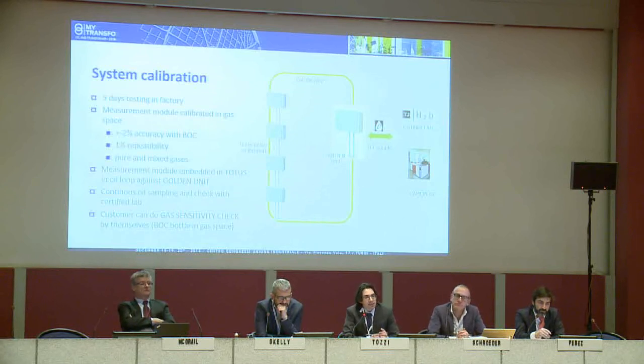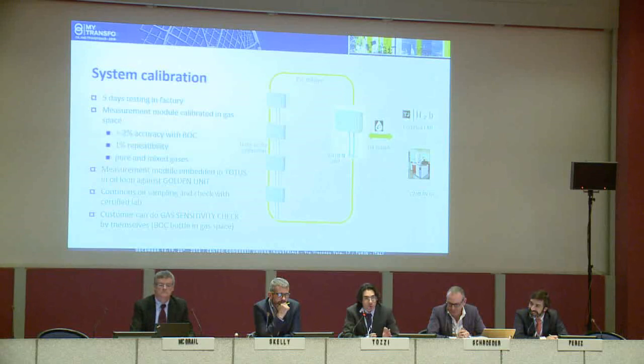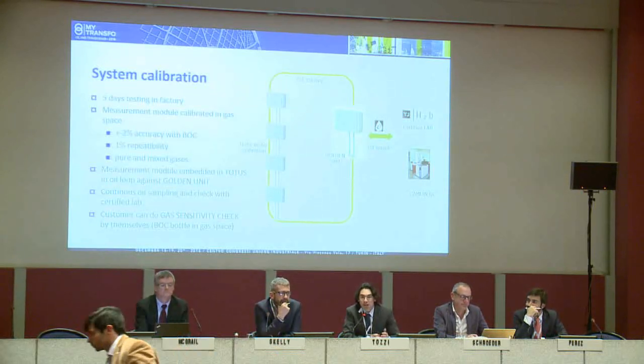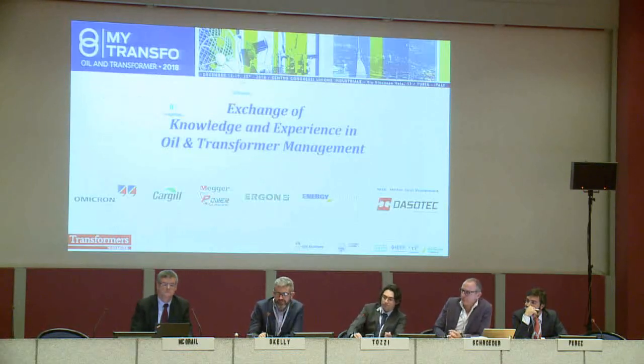Say that in some countries, we have to do a similar process, but using other laboratories, because, for example, in the Far East or Latin America, there is no question. Their lab is the truth. We do it, of course, no question about it. Say that it is possible for the user to do a sort of gas sensitivity check, it's not a calibration, using a conventional BOC bottle with a mix of gas. You can inject this in the field, in the gas space, and check the sensitivity. This applies to both the photoacoustic and NDIR. Thanks. Thank you.